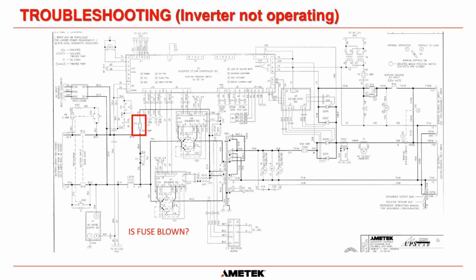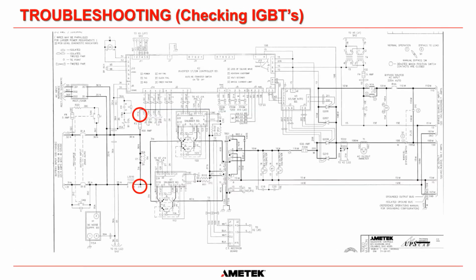So if the fuse is good, the last thing that we need to check is the IGBTs. And there's a very, very quick way to check the IGBTs. So here's our IGBTs here and here. What you do is you get your Fluke and you power down the system. So we want to turn the charger off, and we want to open B1. And then we get our Fluke on resistance, and we measure, we'll put our red lead on this point here, which is the center point of this transformer.